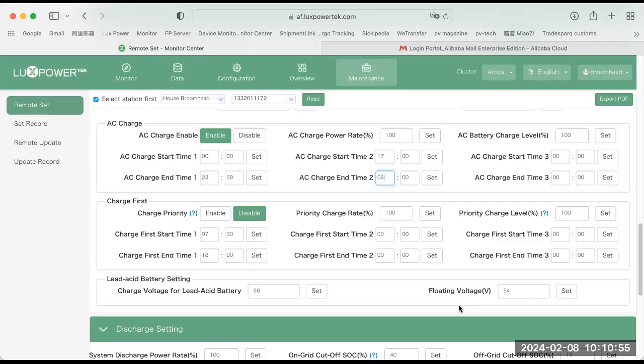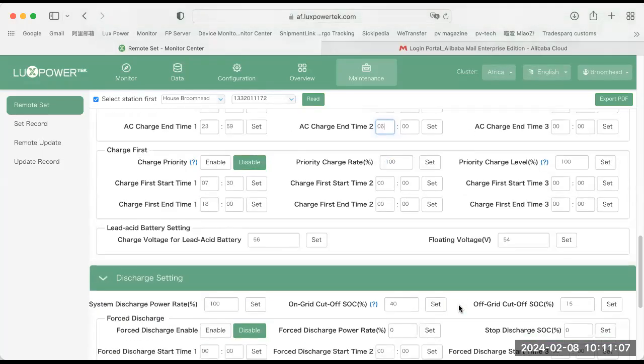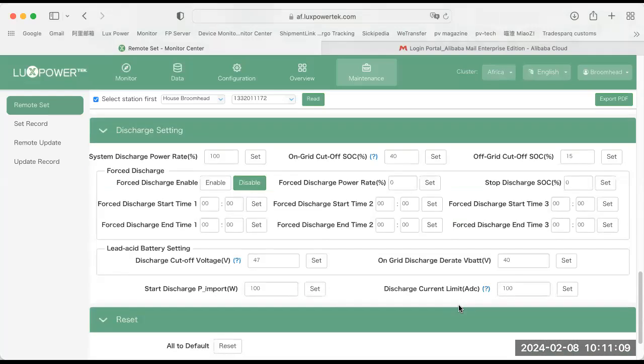So either the AC charge or the charge first, meaning using the PV to charge first, regardless which one of them is active, the battery will just stay there until the grid falls away. Yes, then this rule comes in here. The off-grid SOC comes in. So you can set your on-grid SOC cutoff, as well as your off-grid SOC cutoff.